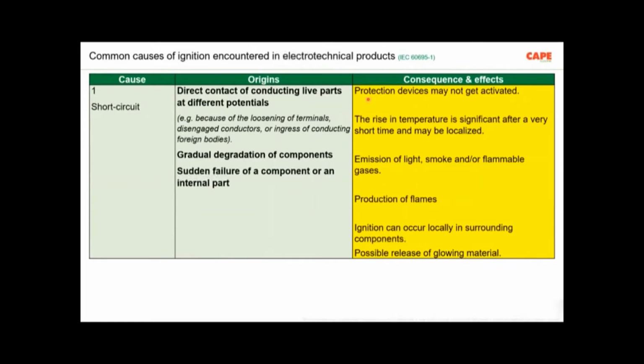One of the factors influencing this parameter is earthing. In case of an earth fault, if your earth fault return path is poor, of course, your protective device doesn't operate. As a result, you will get into trouble. Number two, the rise in temperature is significant after a very short time and may be localized. That means a hot spot inside your equipment in a very small area. And if the temperature is sustained for a longer duration, of course, the short circuit happens.